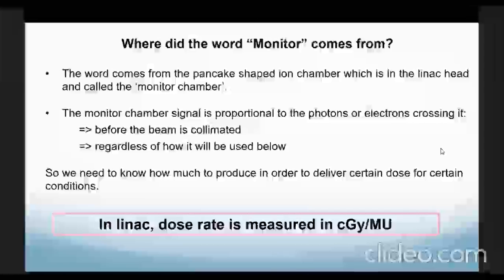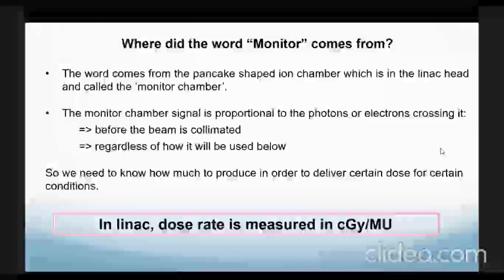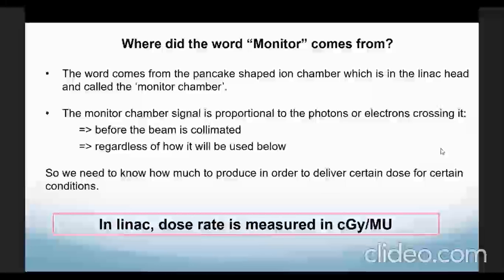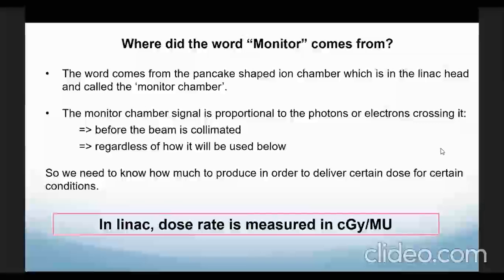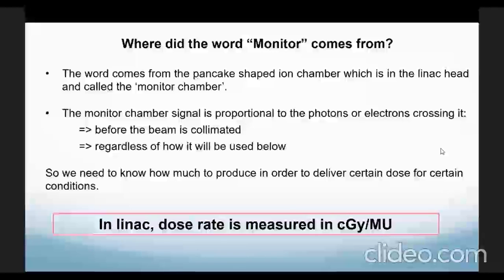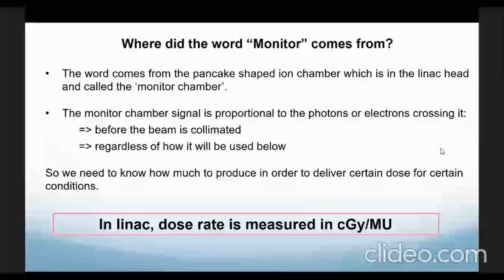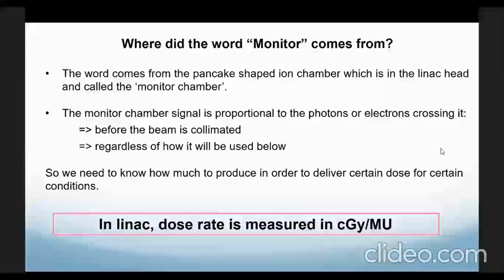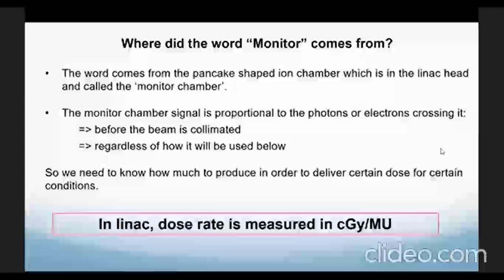Another question is: where does the word 'monitor' come from when we say monitor unit? This word comes from the linear accelerator components — there is a pancake-shaped chamber in the linac head, and that chamber is called the monitor chamber. The monitor chamber signal is proportional to the photons or electrons crossing it, before the beam is collimated, regardless of how it will be used in the patient.